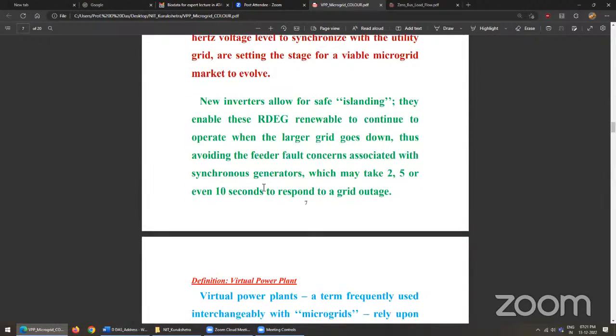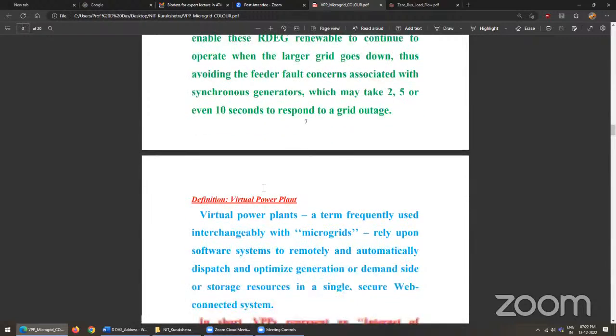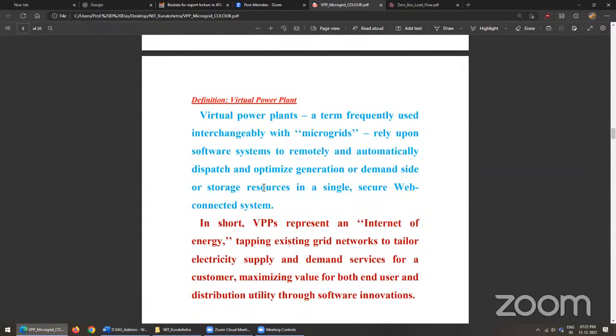So new inverters allow for safe islanding. They enable this RDEG renewable to continue to operate when the larger grid goes down, thus avoiding the feeder fault concern associated with synchronous generators, which may take 2, 5 or 10 seconds to respond to a grid outage. So if there is a grid outage, then this microgrid can be isolated from the grid. And as I told you, as soon as it is isolated, some DGs must operate in droop control mode, because you have to control the voltage and frequency, and accordingly, locally the power can be supplied.